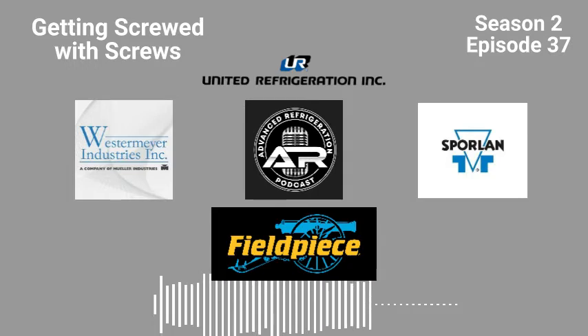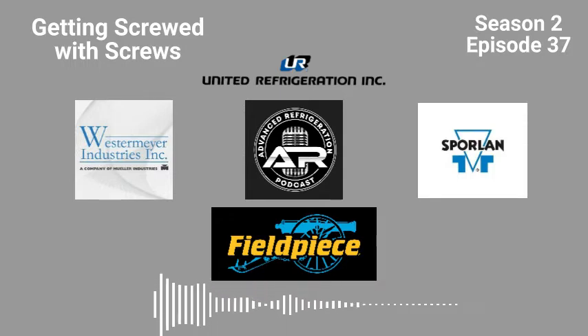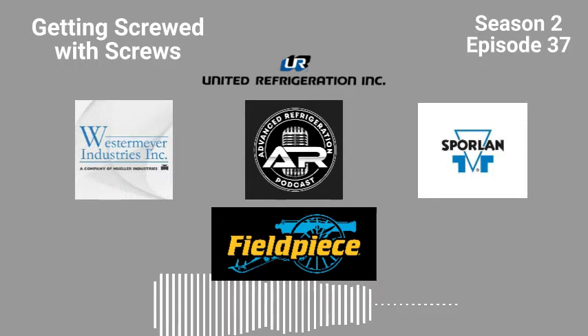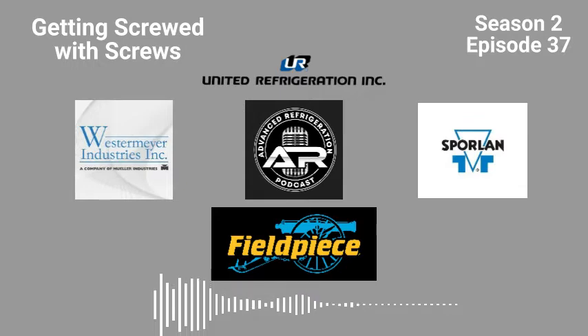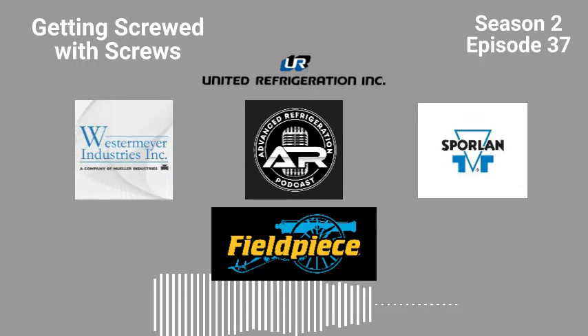Gotcha. Basically, what happens when the filter explodes is it pushes down to the bottom of the housing, and it blocks the housing. Gotcha. And usually it's a tight seal. You may get a little bit out of the packed angle, but I had it wide open and there wasn't anything coming out. So I already knew this was going to end bad. So I throw a towel across my lap and I put my hat down as far as I can go on my face and I start rocking the filter back and forth.